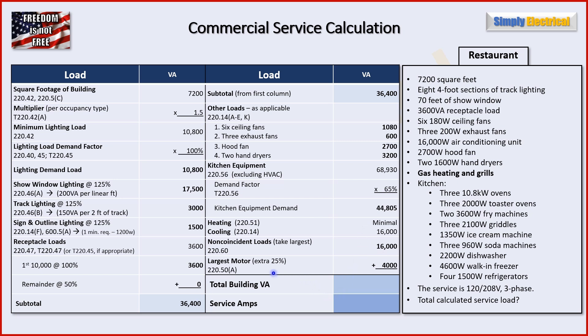Lastly, we have to find the largest motor in the building. Normally that's the AC, even in a restaurant — though you might have a large piece of kitchen equipment like a dough machine that exceeds it, especially if you have multiple smaller AC units. In our case, we'll assume the AC is the largest motor. So we take an extra 25% of the 16,000 VA, which is 4,000 VA, and add that into the calculation.